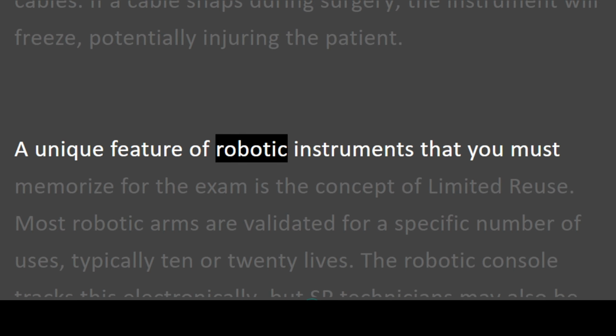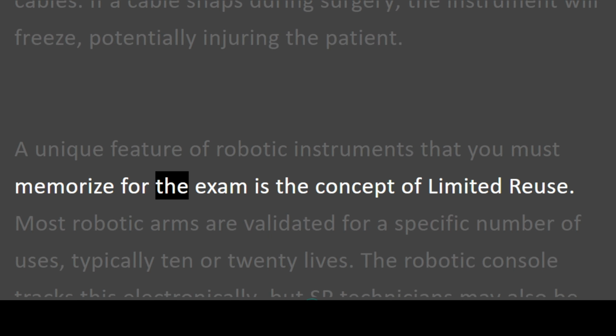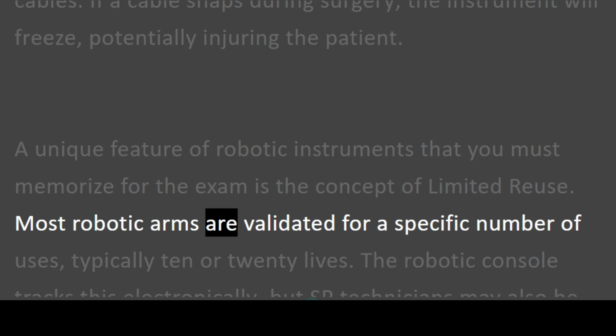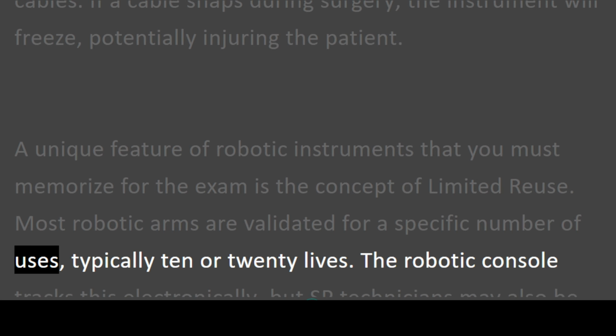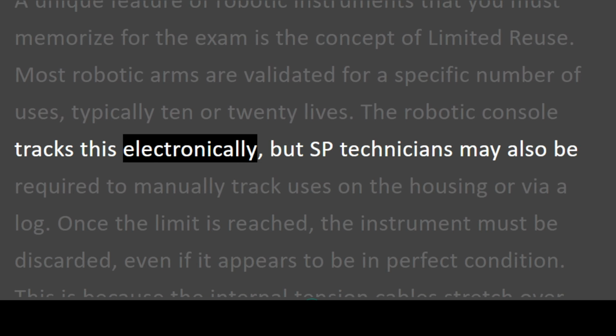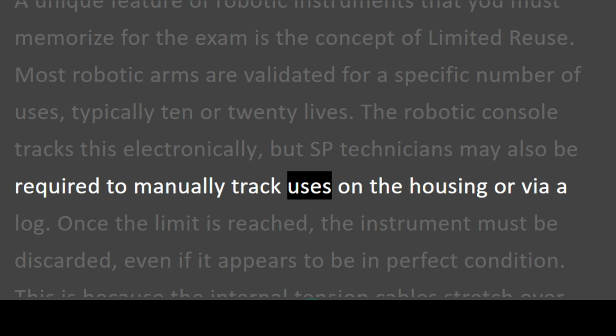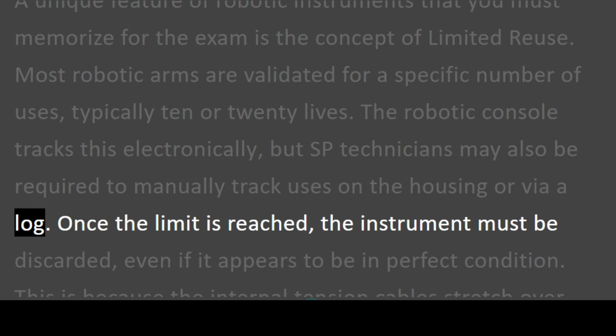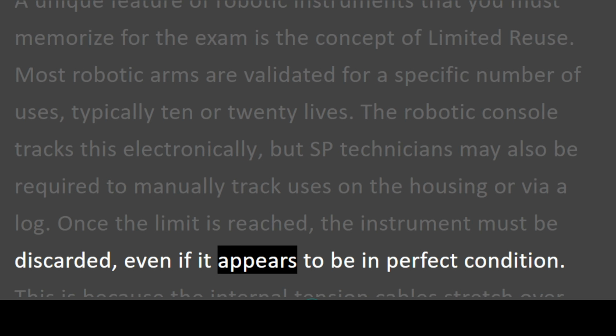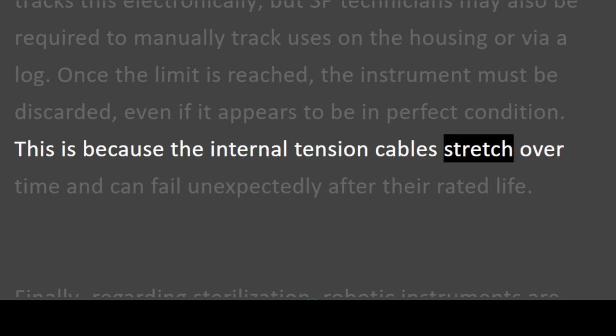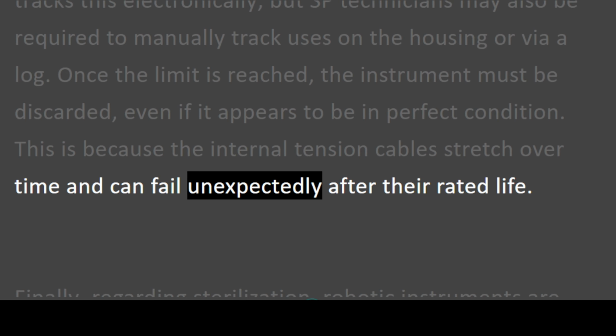A unique feature of robotic instruments that you must memorize for the exam is the concept of limited reuse. Most robotic arms are validated for a specific number of uses, typically 10 or 20 lives. The robotic console tracks this electronically, but SP technicians may also be required to manually track uses on the housing or via a log. Once the limit is reached, the instrument must be discarded, even if it appears to be in perfect condition.